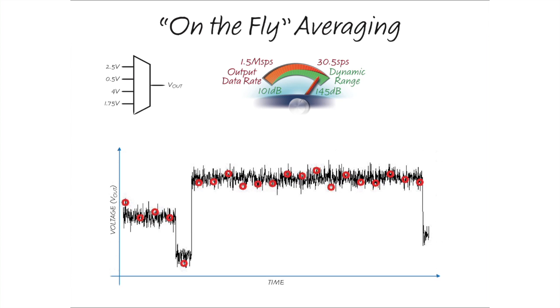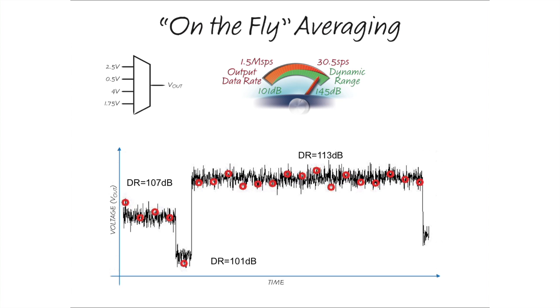In addition, the number of samples taken and averaged on each channel can be tuned to adjust the desired level of noise suppression. For example, the first channel was sampled four times, leading to a dynamic range of 107 decibels. The second channel was sampled only once, resulting in 101 decibels of dynamic range. And the last channel was sampled 16 times, improving the dynamic range to 113 decibels.